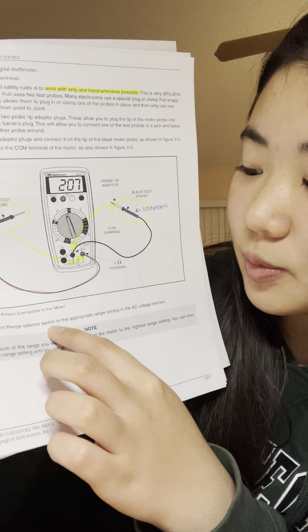Next, perform an electrical safety check. Remove all metal jewelry. Be aware of the condition of the equipment. Do not rely on safety devices. Make sure the grounding prong has not been removed from the AC plug. Keep test equipment and tools organized. Do not work on a wet floor. Work with one hand whenever possible—this is important, always work with one hand. Move slowly and deliberately, do not work by yourself, and do not get distracted.